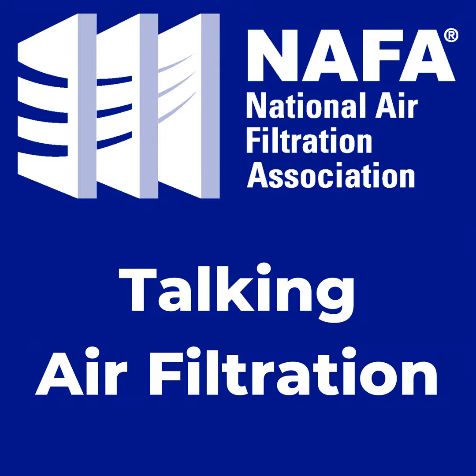We had this filter that had comparable, maybe a little bit lower by 0.1 inch, initial resistance, and it had similar dust holding properties because of the way the media was manufactured. The media made for this filter was really an interesting extended surface area type media. It wasn't just a straight coated nanofiber media. They really designed it well to have good upstream dust holding performance as well as the nanofiber there for the efficiency. And you could see that for similar mechanical efficiency, you had a lower pressure drop, and they were able to design this media to have roughly the same dust holding capacity.